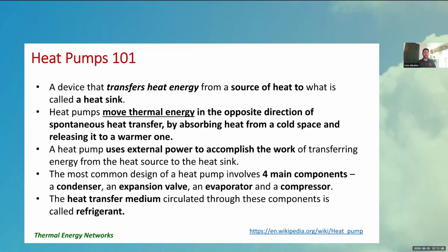We can take that hot refrigerant and blow air over it — that's the most common approach, a forced air system heating or cooling through ductwork. We can also run water over that refrigerant coil and create water temperatures up to about 135-140 degrees. Some commercial heat pumps coming out now can go hotter, but for today, with equipment we know is robust, a good design temperature is between 135 and 140 degrees.